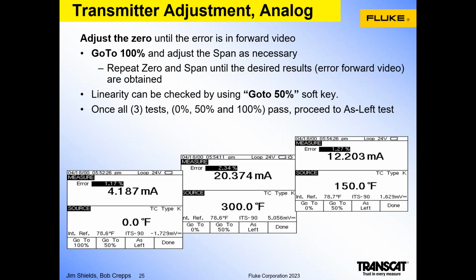In the event that the test fails, there are two methods of adjustment. One is analog, and that's the example I gave earlier, where old style analog instruments have a zero and span adjustment, where the 4 milliamp signal is adjusted with the zero potentiometer, and the 20 milliamp signal is adjusted with the span potentiometer. And that test is performed, making the adjustments and assuming it's within tolerance, and then a linearity check at 50% to ensure it's in spec as well.